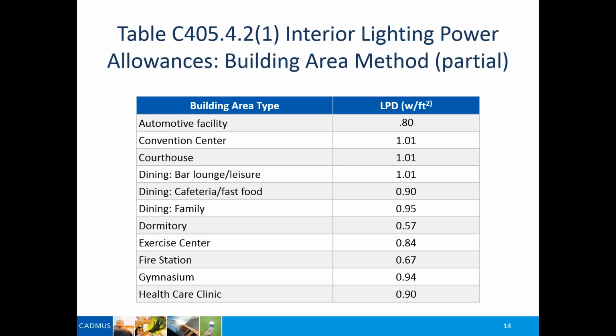That said, look at the lighting power densities in this facility. If you've been keeping up with LED design, you might be saying to yourself, I can go below that. And indeed, I have friends in Seattle, electrical engineers, designing down to less than 0.5 watts per square foot. One fellow who's really advanced is going down to 0.3. Add controls to that and you get an incredibly efficient lighting design.